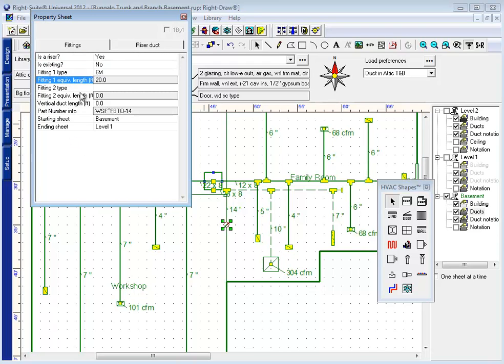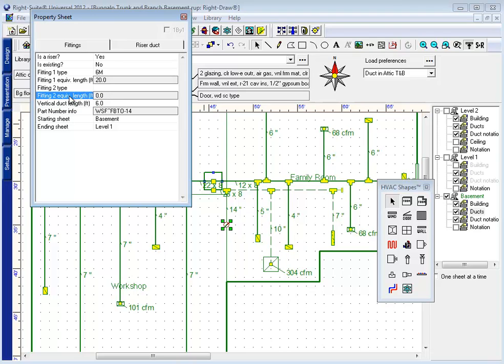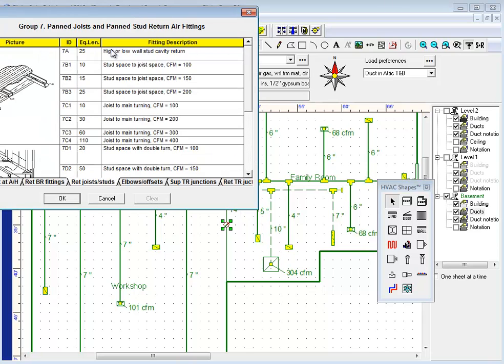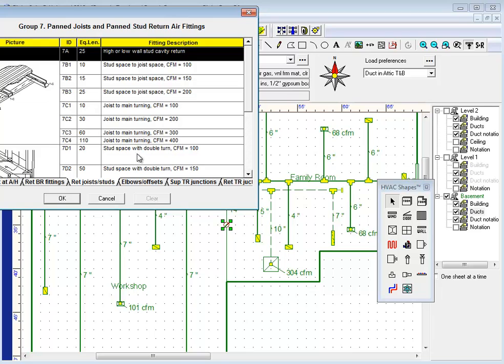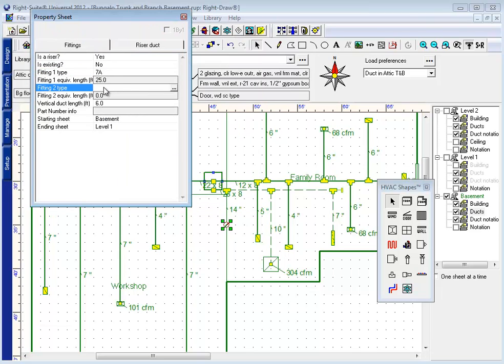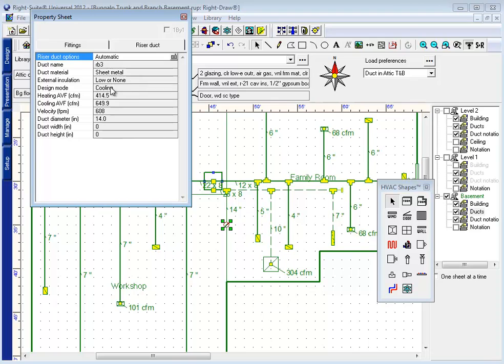And when I make this a riser duct, I get to tell it what the length is. So how far up the wall is this thing going to go? Now, the program automatically chooses the fitting here, which I can then select as a high wall stud cavity return space. I can also choose an elbow for my second fitting.